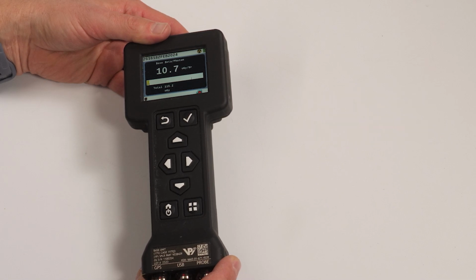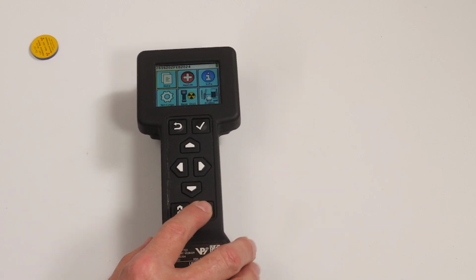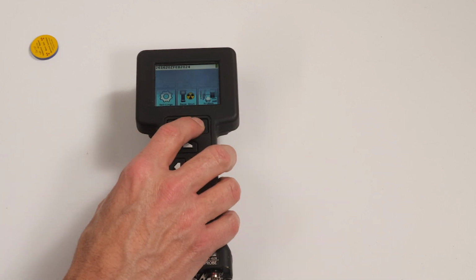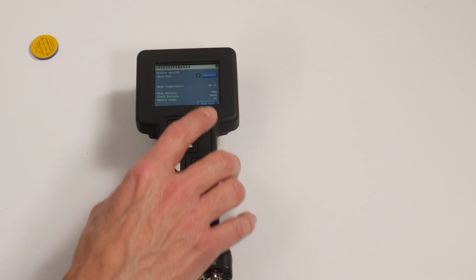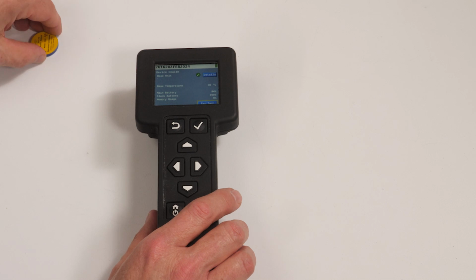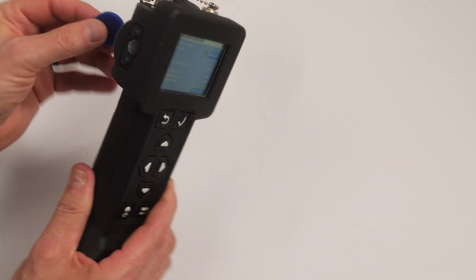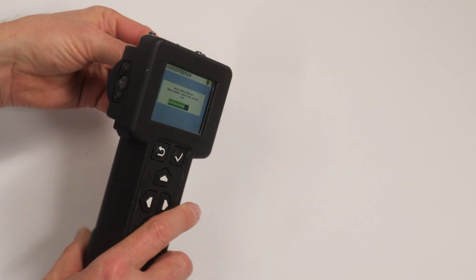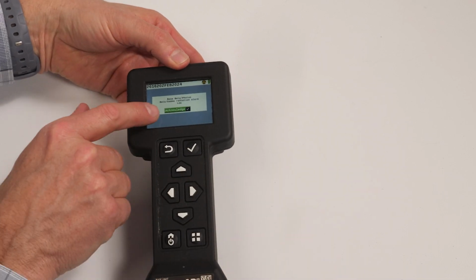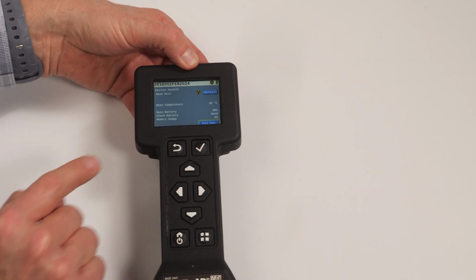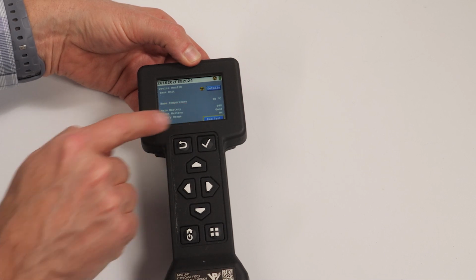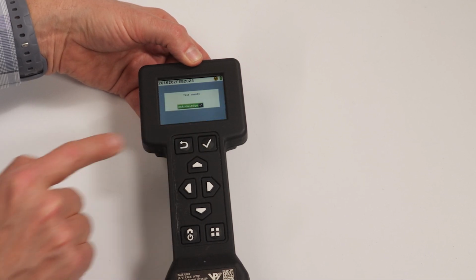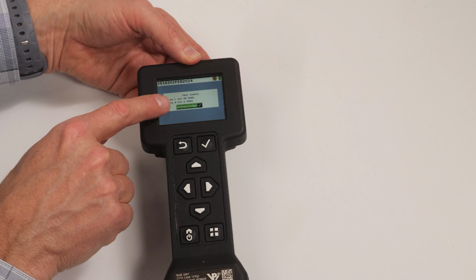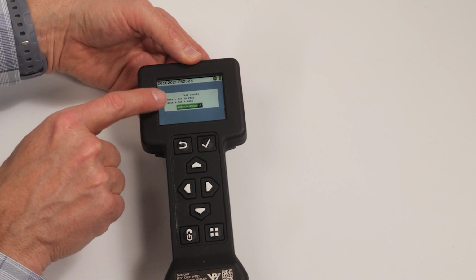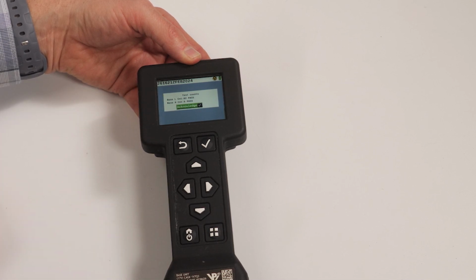Next, we'll perform a RAD test. Press the menu key, highlight Health, and press Enter. Place the cesium-137 check source in direct contact with the base unit on the small crosshairs this time, which is the location of the high-dose GM tube detector. Acknowledge any threshold alarms by pressing the Enter key, if applicable. Highlight the RAD test button and press Enter. Leave the base unit in direct contact with the check source for 1 minute.